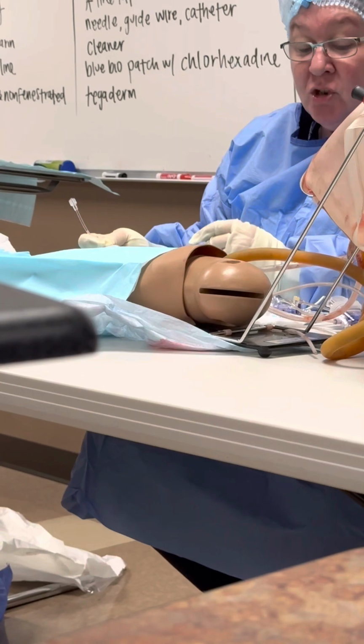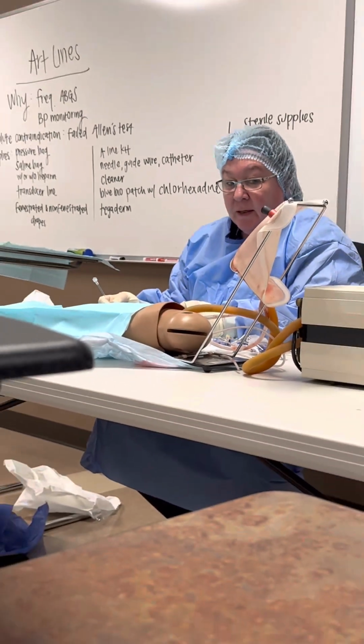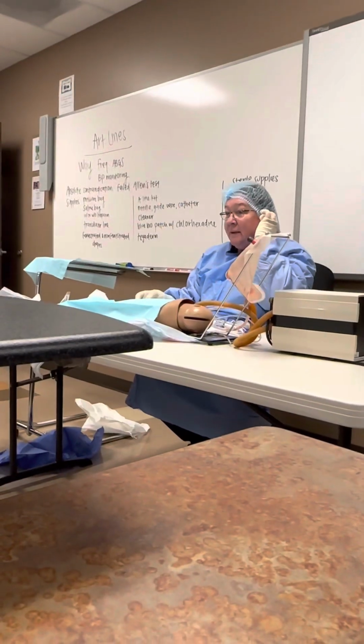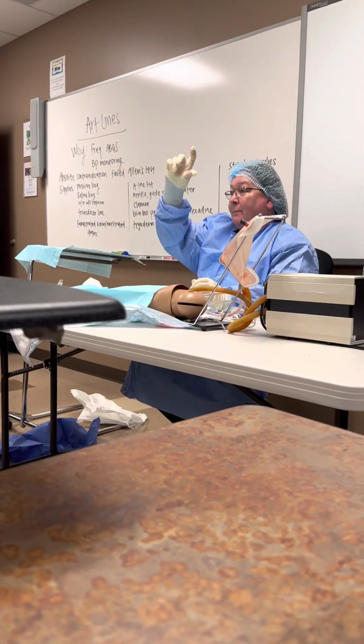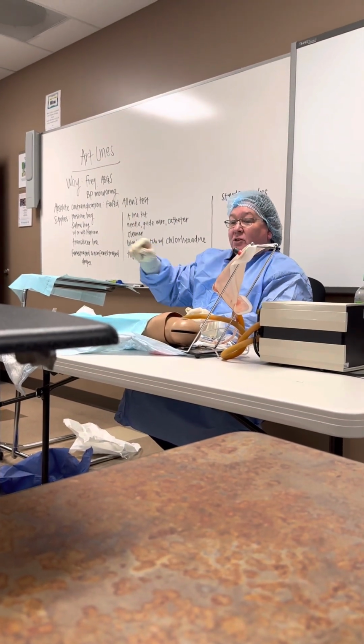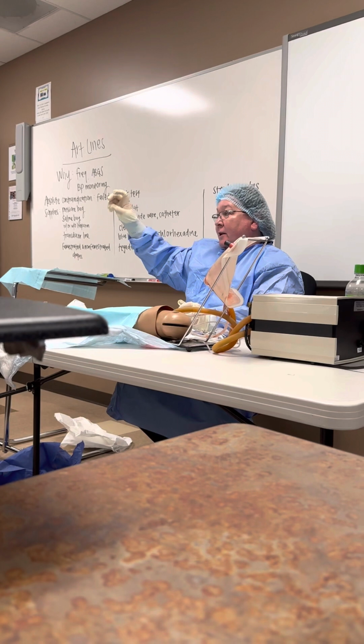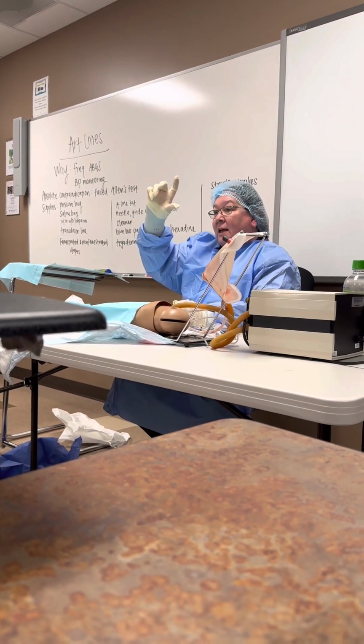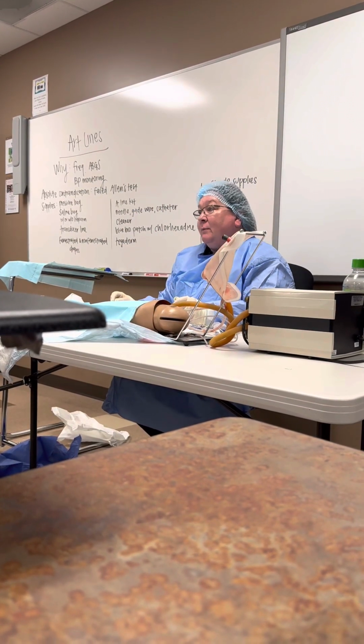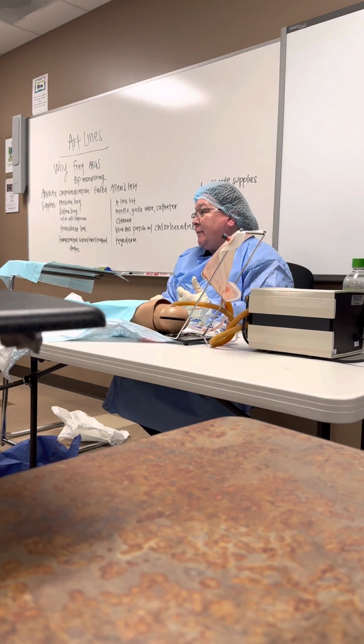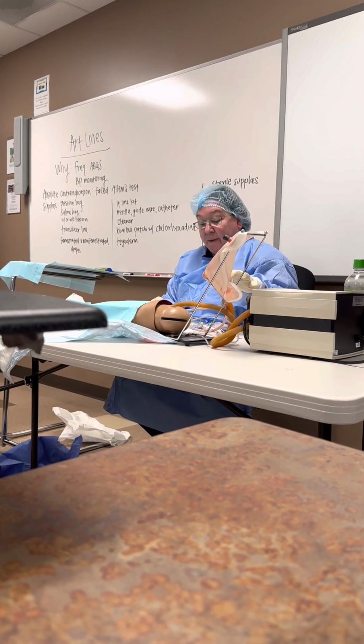As far as troubleshooting goes, there's only a couple things. That waveform can become dampened, and when we say dampened, it's just like half of what it should be. So instead of that nice tall dicrotic notch, just like a pulse ox waveform, it would only be half of what it should be. We see that when we get clots or air bubbles in. So then we would just need to clear that.